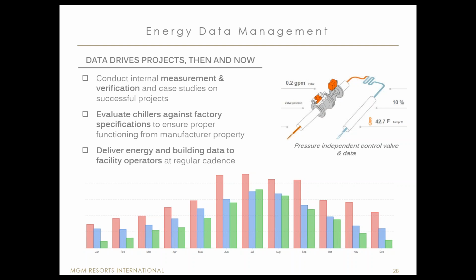I've got a picture here of a pressure independent control valve and some of the data. We had a property that had a significant drop in energy consumption. We didn't know why. We asked the property, and they said, oh, we put in 30 of these large pressure independent valves on air handlers, and we're saving a lot of chilled water, and that's cascading back to our central plant. We were able to verify that, and through that data we ended up rolling out that project to 7 additional properties, performed measurement and verification, and in some cases reduced the runtime of an entire chiller for a year by reducing energy demand from our air handlers.